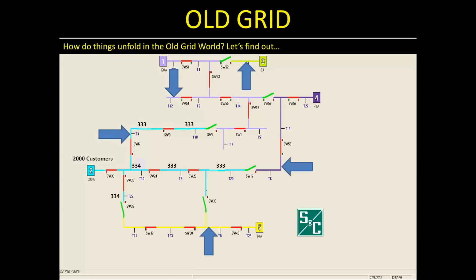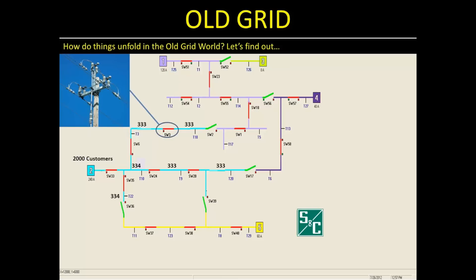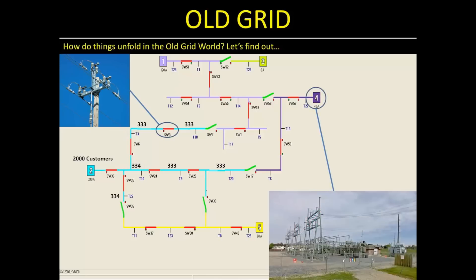Typically, these have three wires and big switches on them. These switches don't measure currents or voltages, don't do any processing, and don't communicate with anything. If you want to operate them, you need to go out and open and close them manually. Some of these devices are shown in the diagram as closed and colored red, while others are open and shown in green. This system includes five substations that provide power to the main feeders, and each feeder is color-coded to match the color of the substation from which it's drawing power.